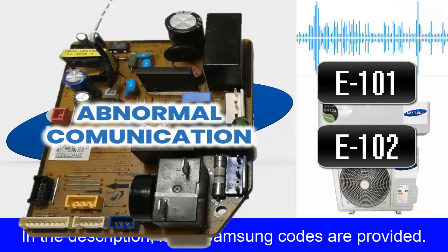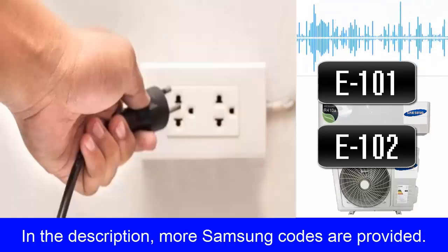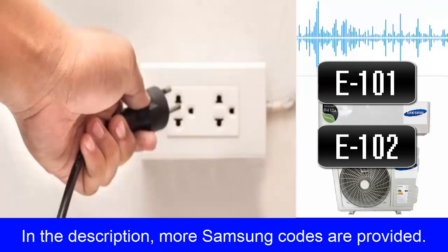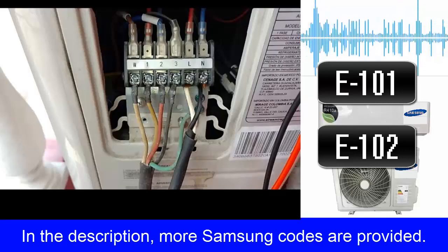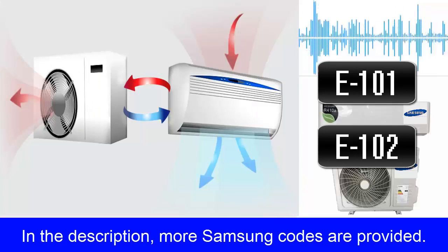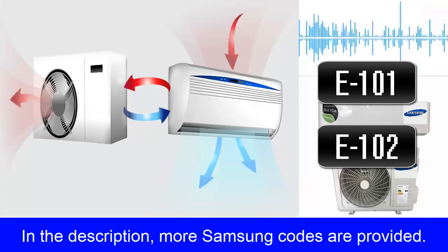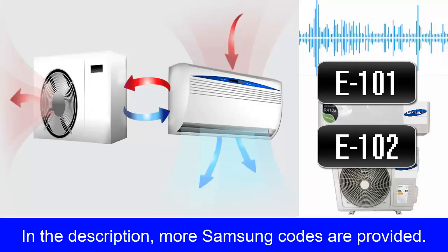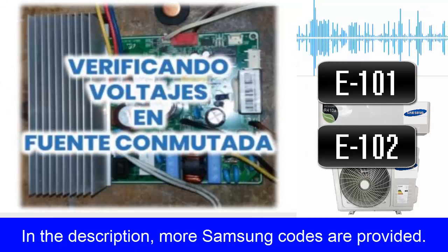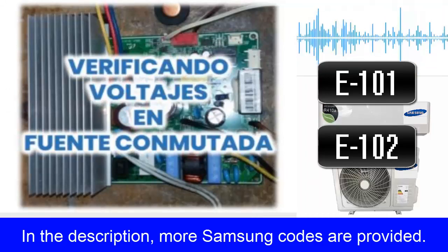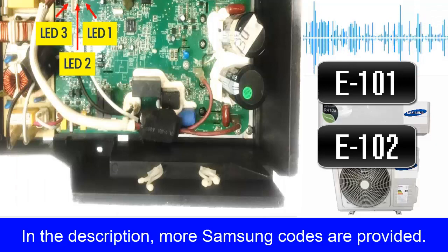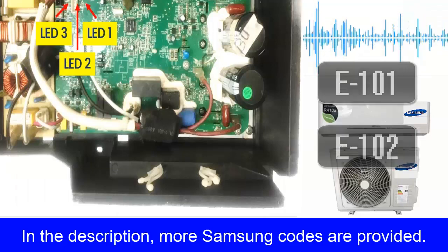1. Fault represented by error codes E101 and E102. These indicate communication problems between the indoor and outdoor units. A. Disconnect the equipment for several minutes. B. Check the communication cable connections. C. Ensure there are no nearby electromagnetic interferences, and inspect the cable conditions. D. Verify that both the indoor and outdoor unit status LEDs are on.